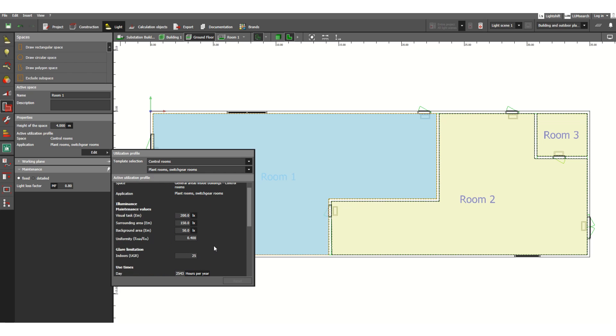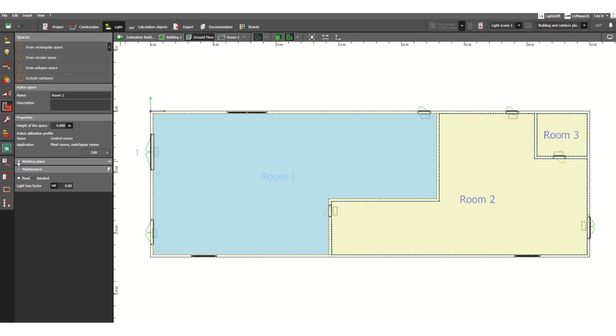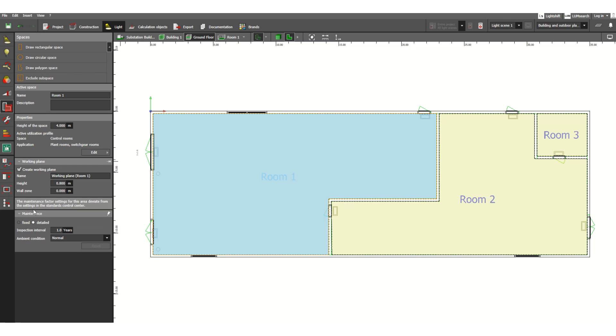Under the 'Create Working Plane' tab, the working plane height is 0.8 meters by default. You can customize this to 1 meter as per project specification. Under Maintenance, the maintenance factor — also called light loss factor — is fixed at 0.8 by default in DIALux Evo. If you want to customize it, click Detail. You can set inspection level, inspection interval, and ambient condition — normal, clean, or very clean.